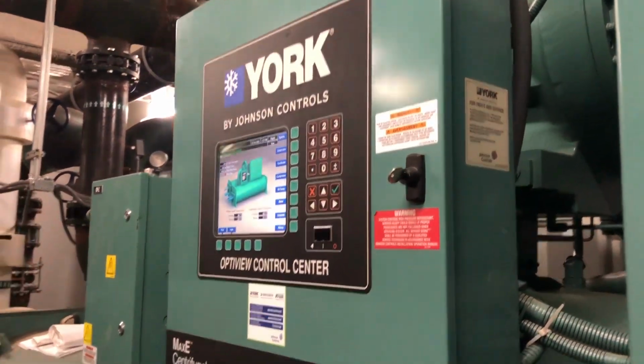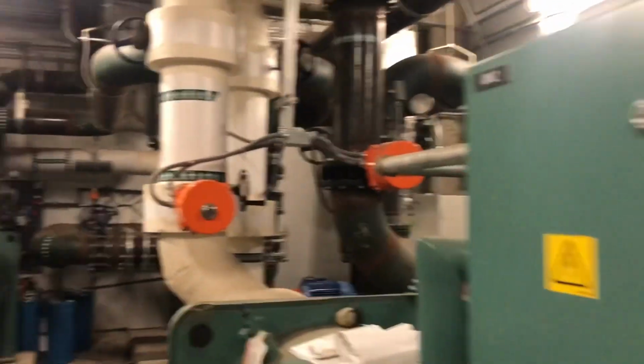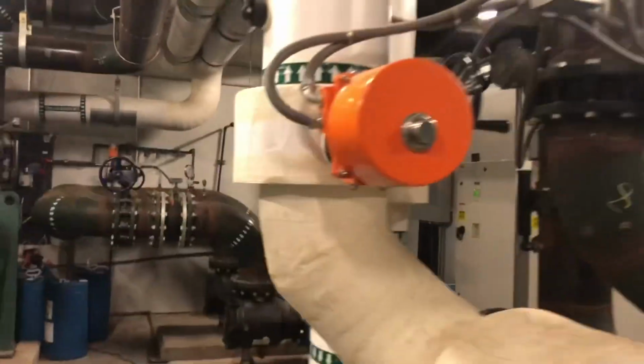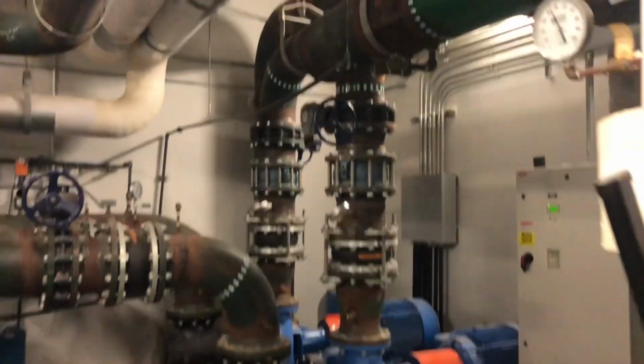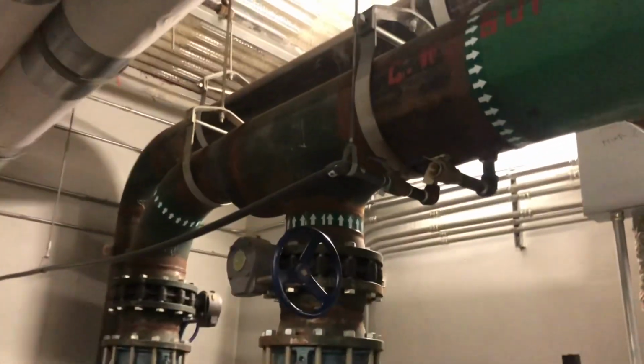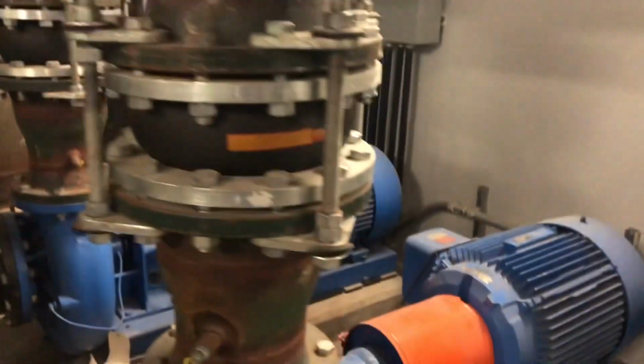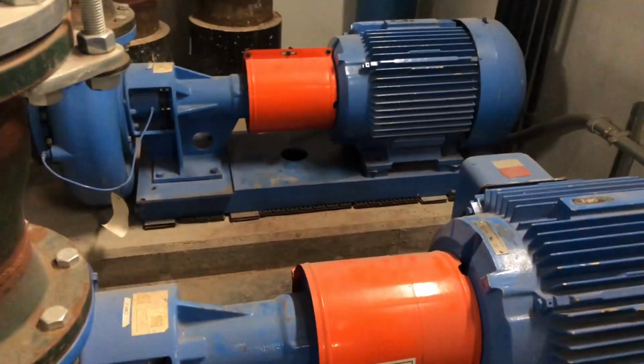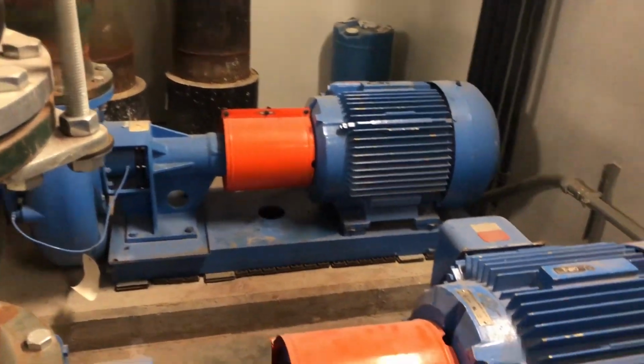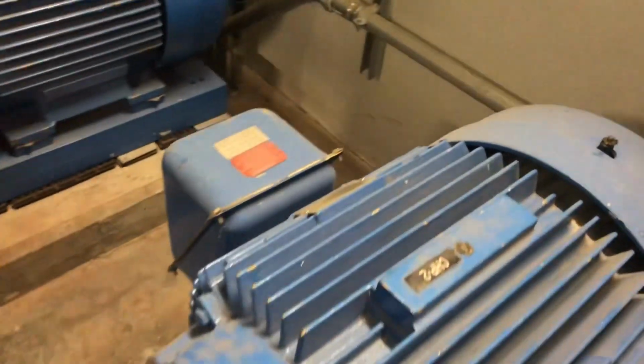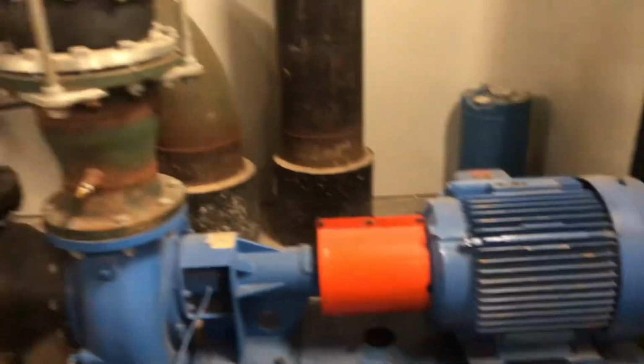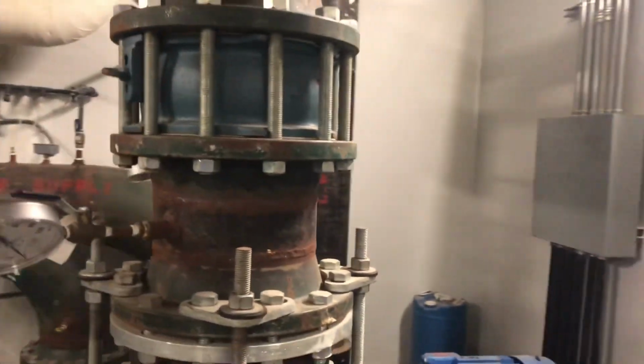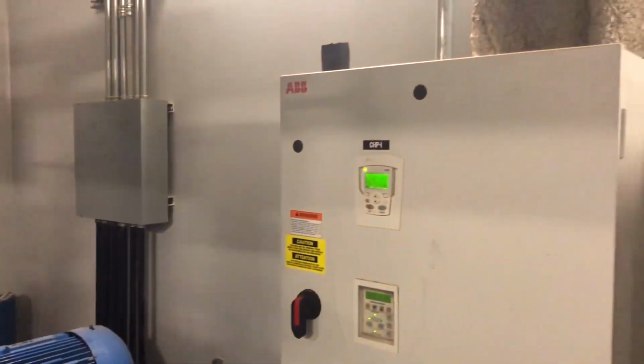So I took the noise out of this video so I can explain to you much better, and you don't hear all the noise in the background. So I'm gonna give you just the basic explanation on this video. Okay, so right now we're looking at the condensing pumps. These pumps will pump water to your condensing side of the chiller, and it will also pump water to the cooling tower to cool down the water.